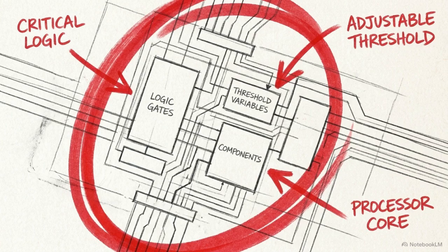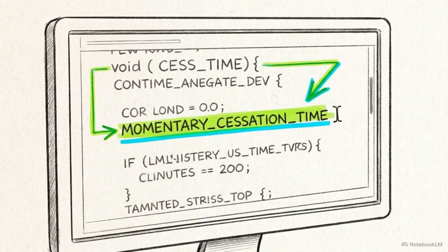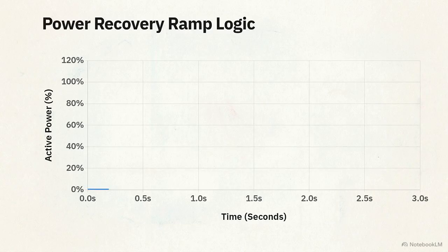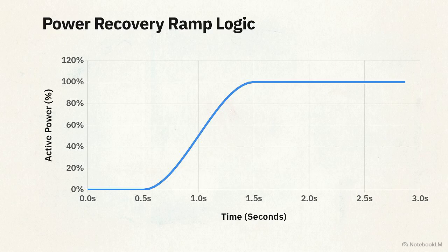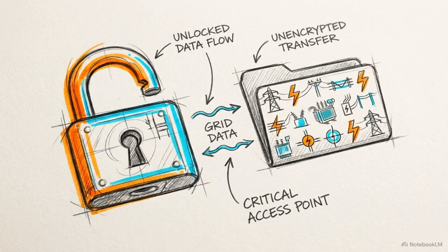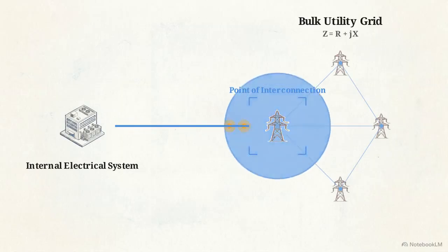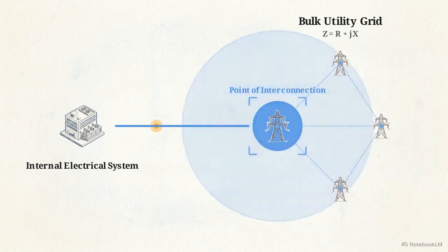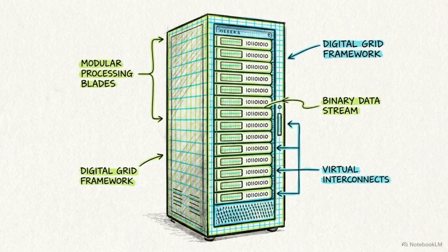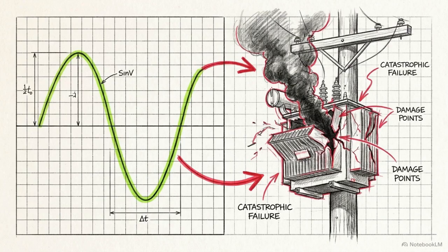Engineers must map the exact protection settings, such as AC and DC undervoltage trip thresholds, to build an accurate simulation. This includes programming precise momentary cessation walk-in times to model how the facility recovers and ramps power back up after a fault clears. Engineers also require unencrypted AC network impedance data to accurately map how the data center's internal electrical system couples with the bulk grid. An EMT model is only as reliable as the proprietary hardware logic fed into it. Relying on generic assumptions leads to simulated safety but real-world instability.